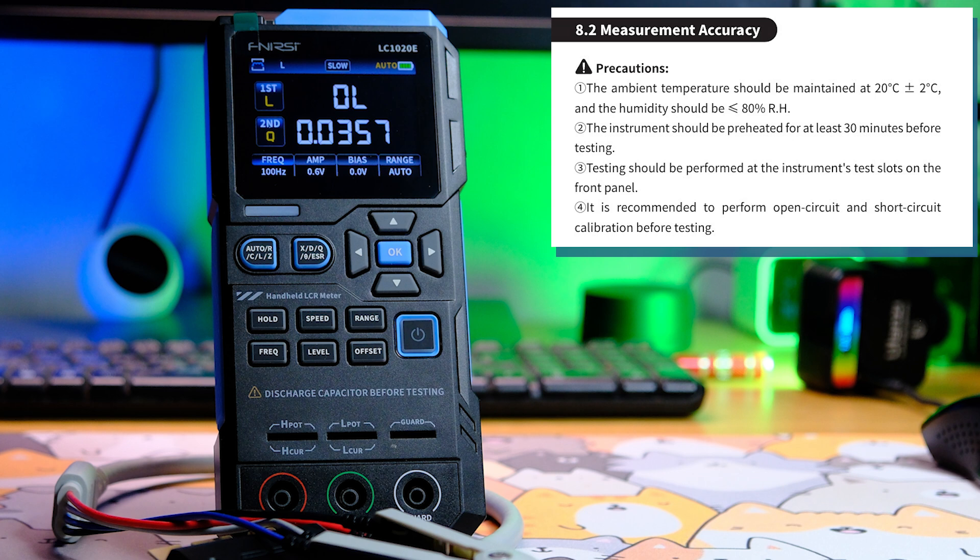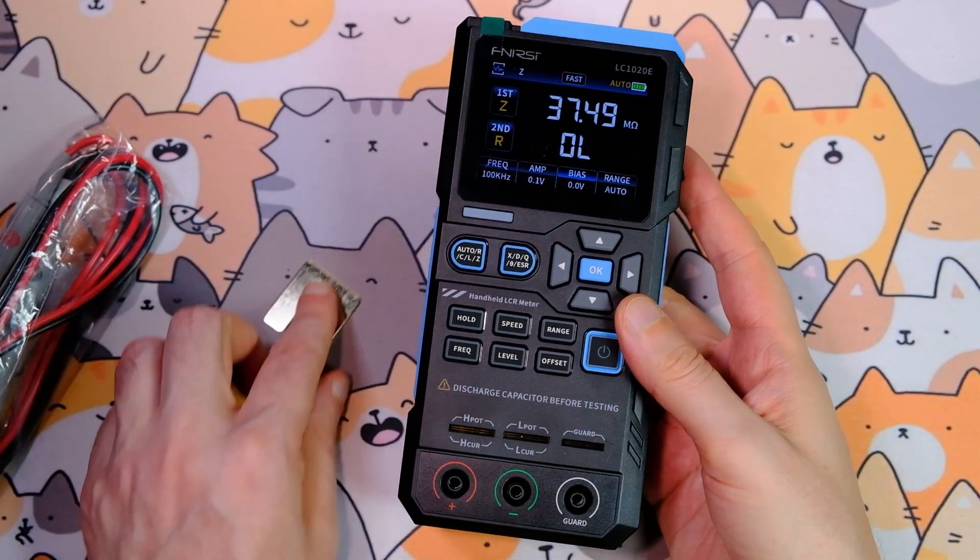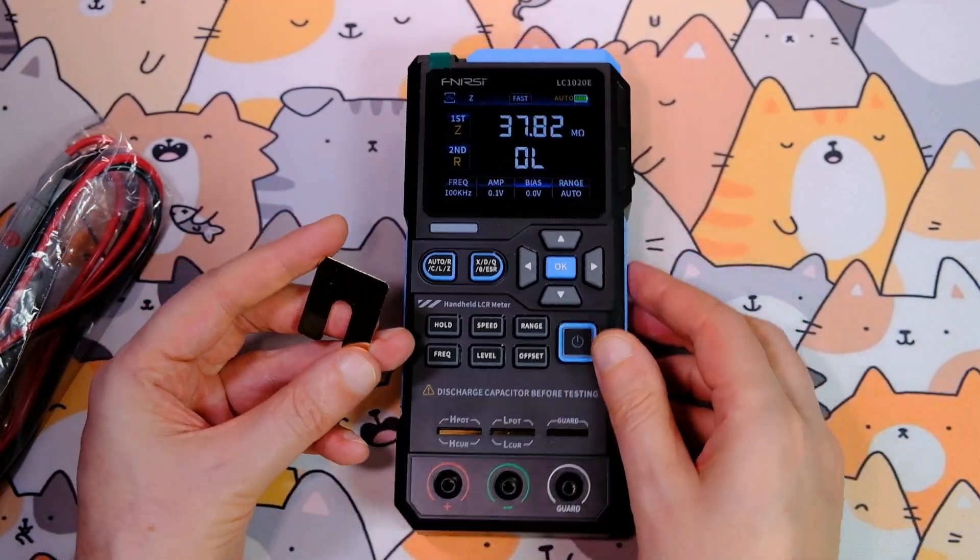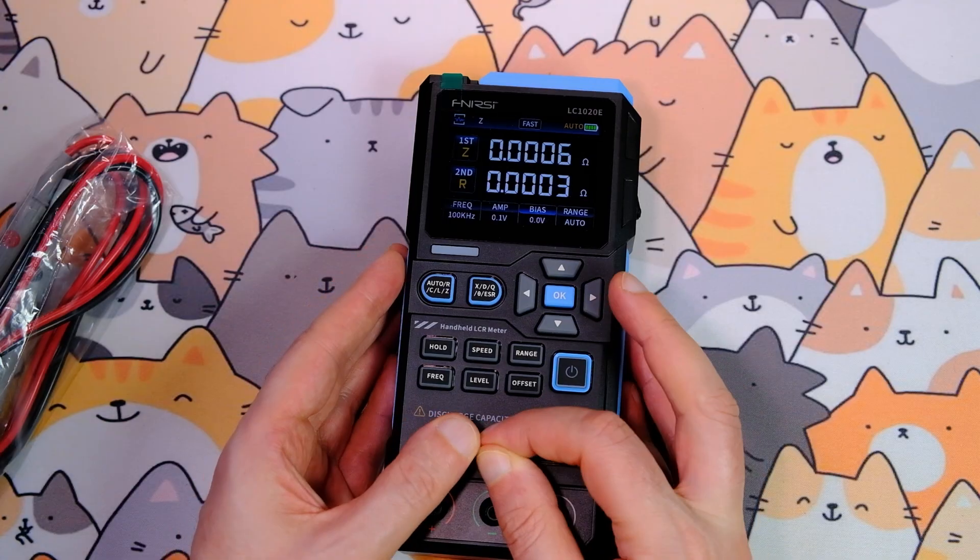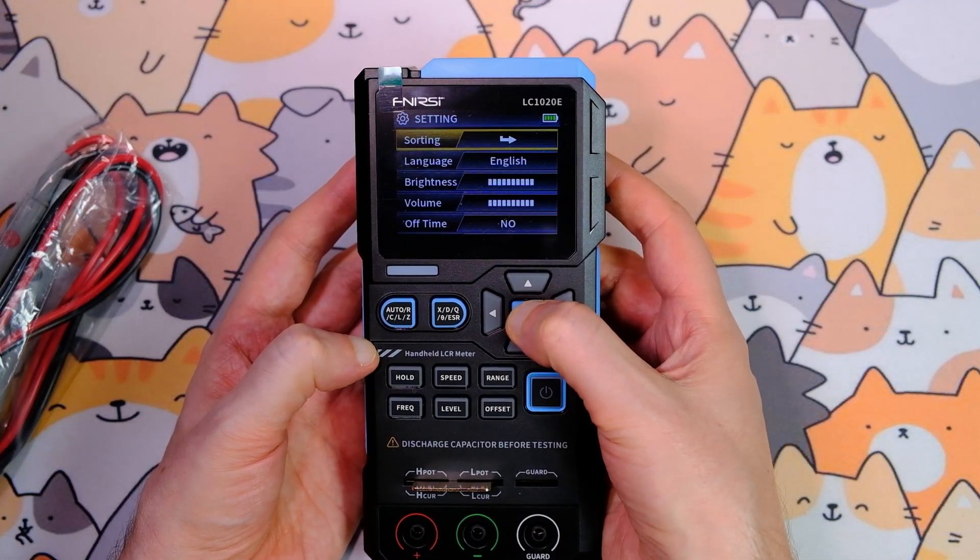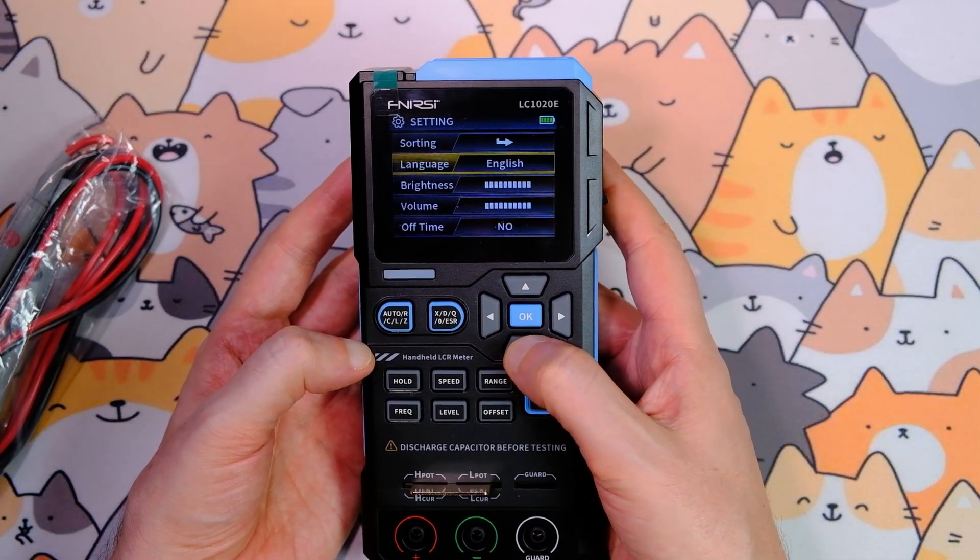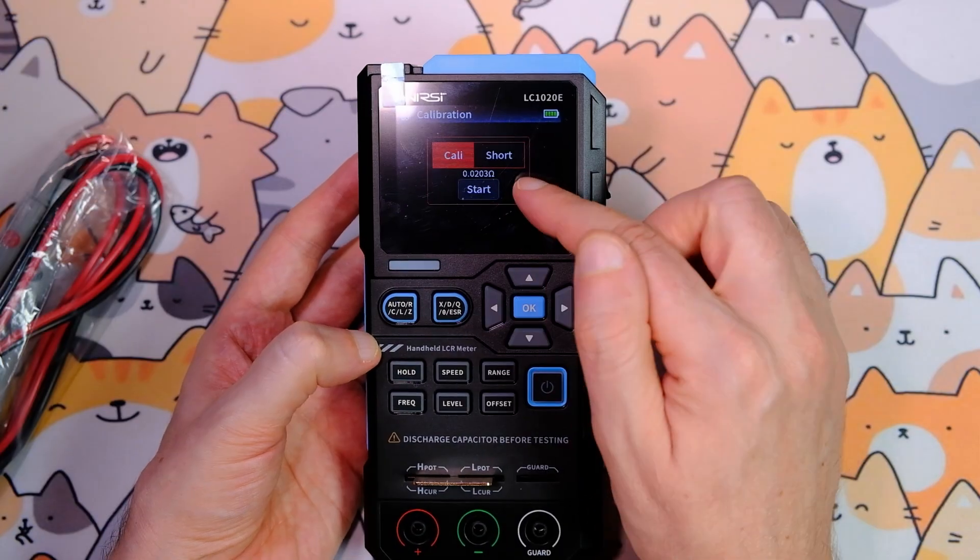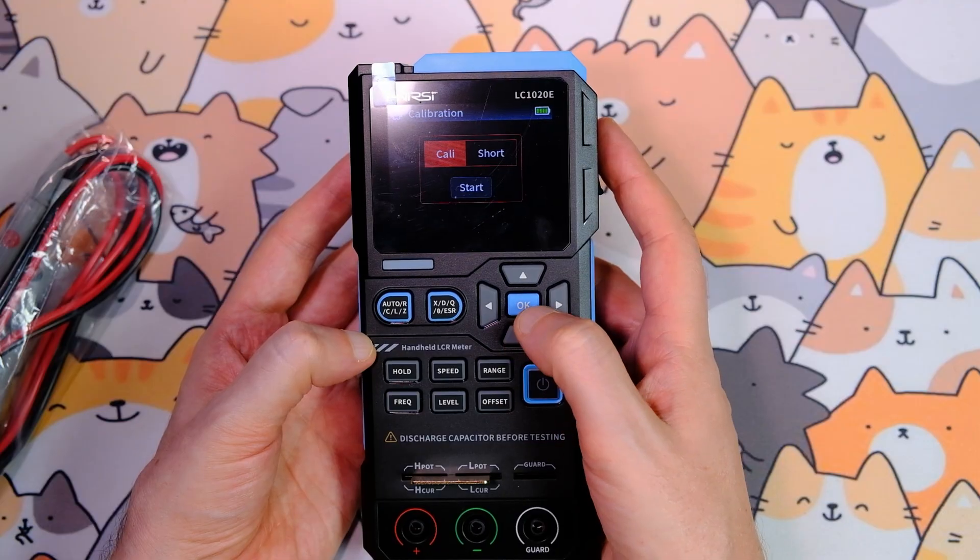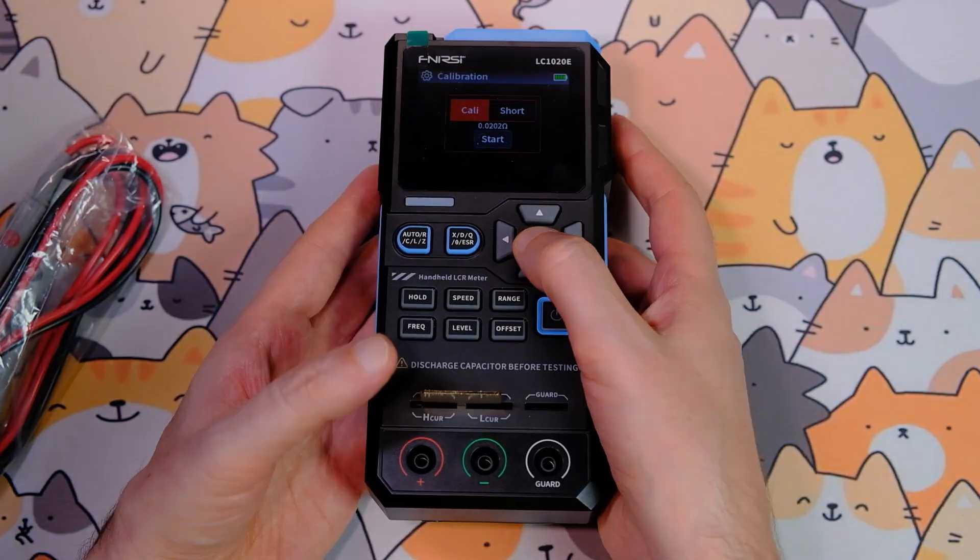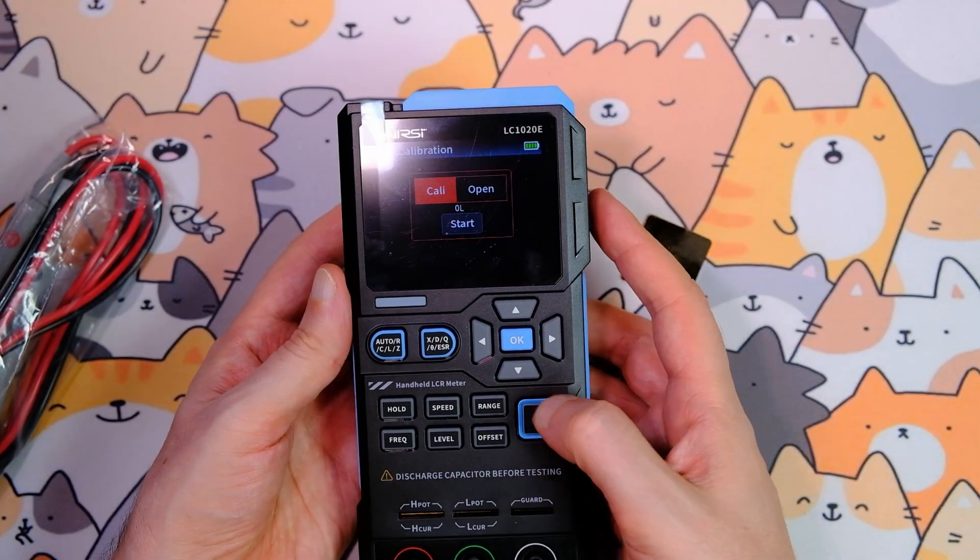You need to calibrate with the channel open and closed. The kit comes with a calibration plate. Insert it, press OK, and go to the device's menu, look for calibration. First, calibrate with the closed channel. I'll do that now, it takes some time. Then remove the plate and calibrate with the open channel.